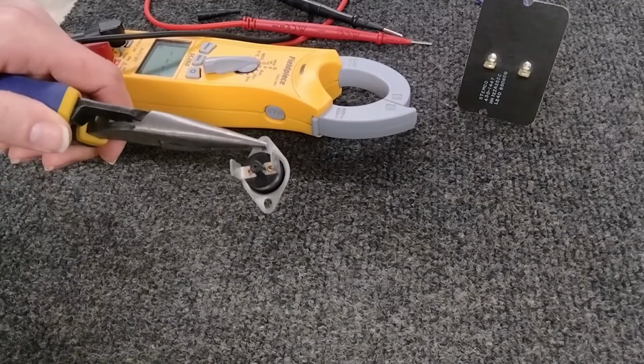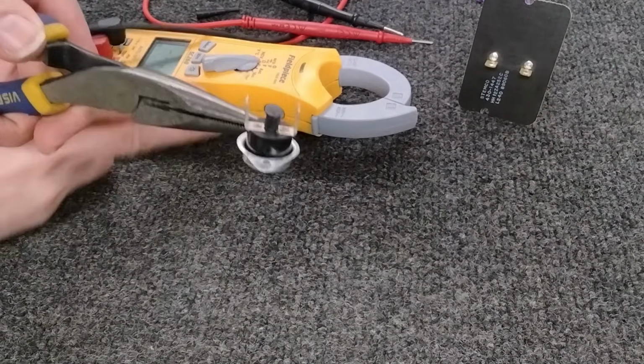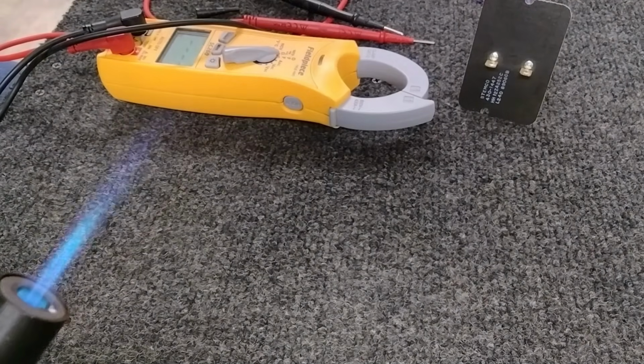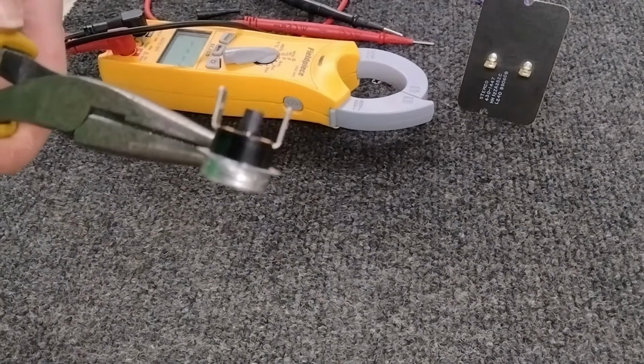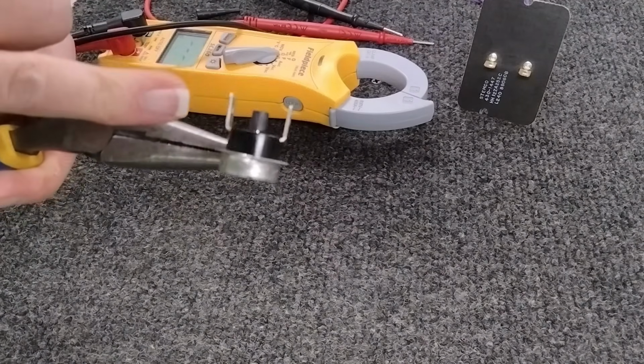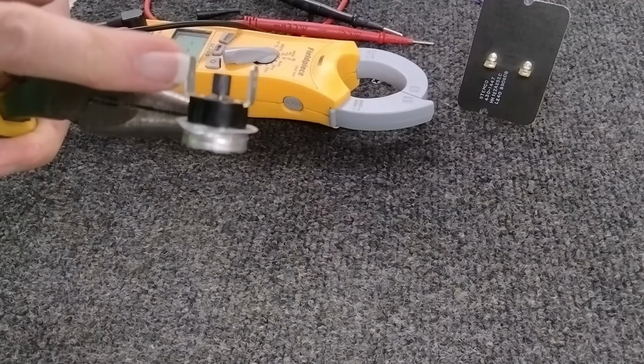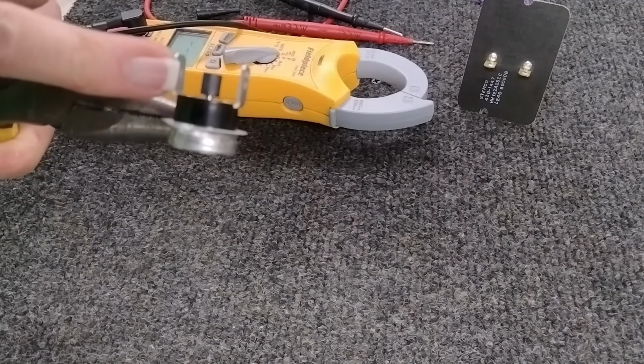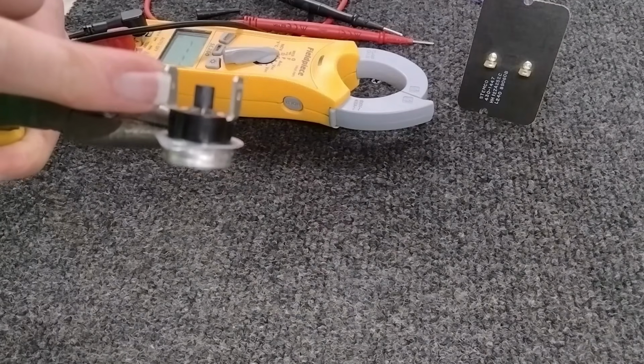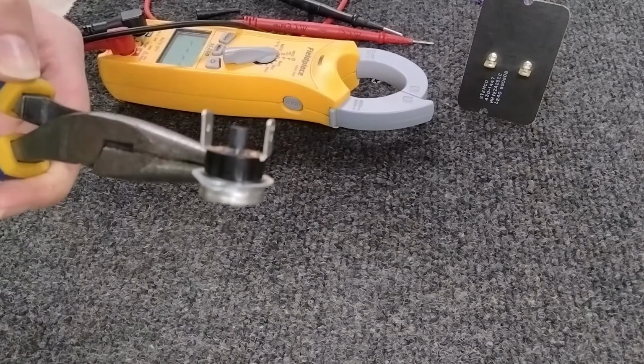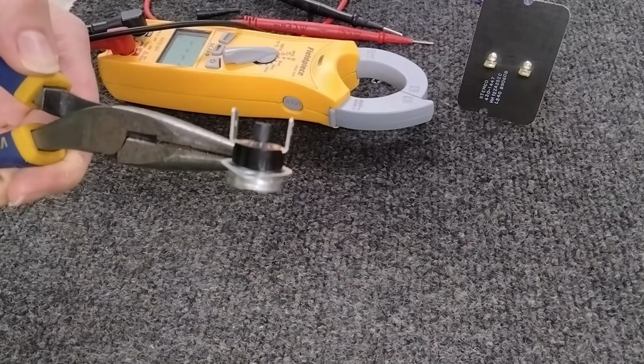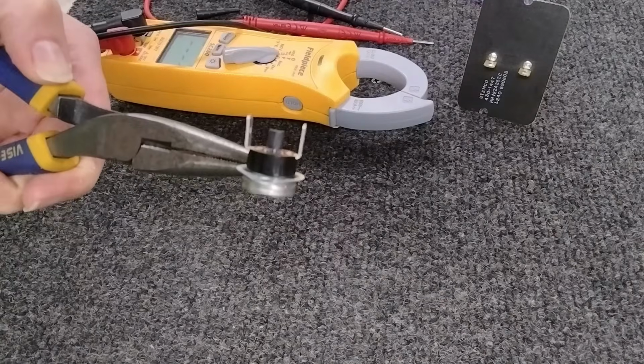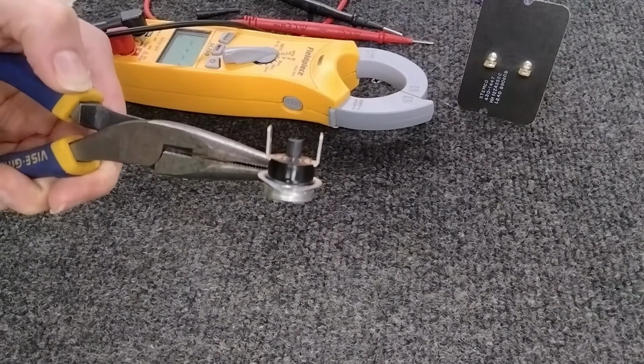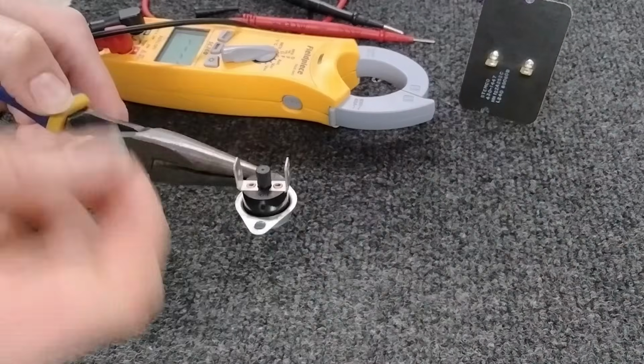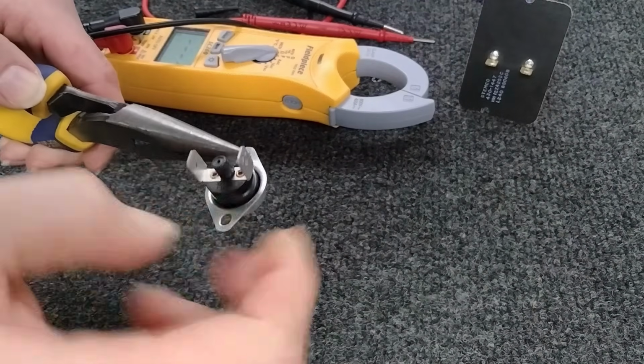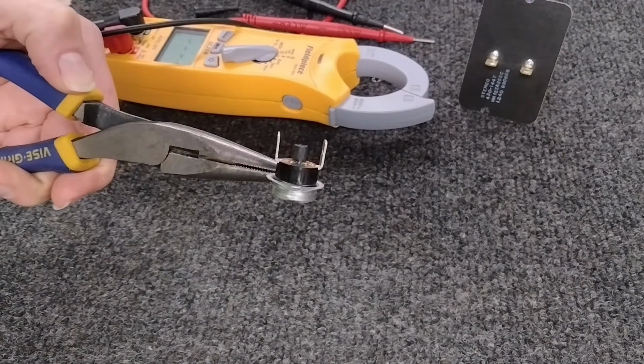It's going to be the same thing with these rollout switches. They're going to have a higher temperature tolerance. And there we go. As you can see right there, this is why it's called a manual rollout switch. It's a manual reset rollout switch. These are put into place for a very important reason. If it detects rollout, it's going to pop, which means you or the technician has to go up to the furnace and manually reset it. We're going to give it a minute to cool down, and then I'll show you what I'm talking about.